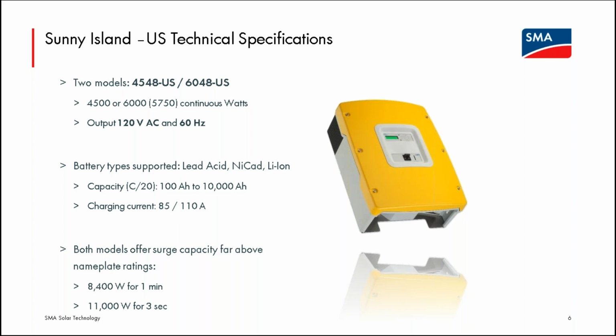Since this device was designed to be an off-grid device, it has quite a bit of surge capacity so that someone can start up critical loads that have a motor, some large current draw when they're starting up, a well pump, things like that, that require a very brief but high current pulse. Both models of the Sunny Island can provide 8,400 watts for 1 minute or 11,000 watts for 3 seconds.